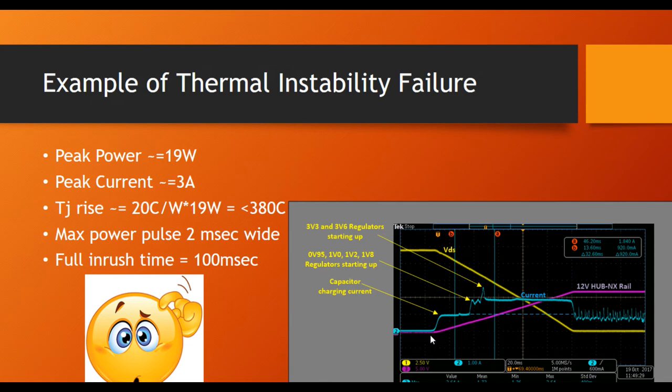That was required to charge up the capacitor banks, and this added together to create a very high power dissipation within the device which was enough to trigger off the Spirito effect because the cells went into a thermal runaway. They were being driven below the or in the positive temperature coefficient region of the transfer curve.